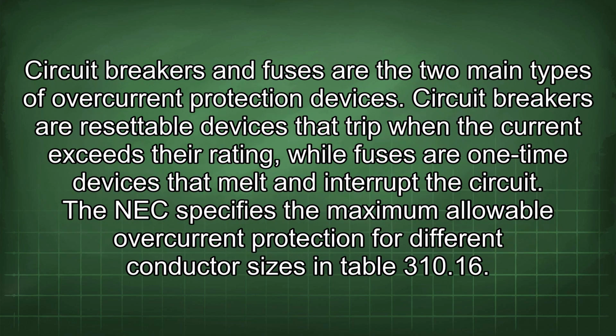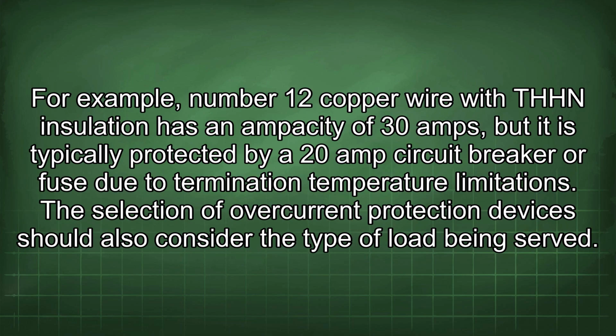Circuit breakers and fuses are the two main types of overcurrent protection devices. Circuit breakers are resettable devices that trip when the current exceeds their rating, while fuses are one-time devices that melt and interrupt the circuit. The NEC specifies the maximum allowable overcurrent protection for different conductor sizes in Table 310.16. For example, number 12 copper wire with THHN insulation has an ampacity of 30 amps, but it is typically protected by a 20 amp circuit breaker or fuse due to termination temperature limitations.